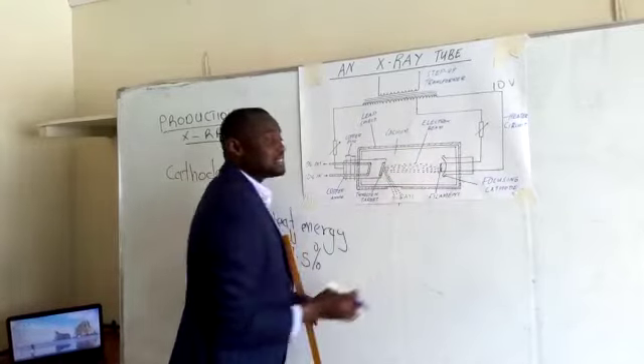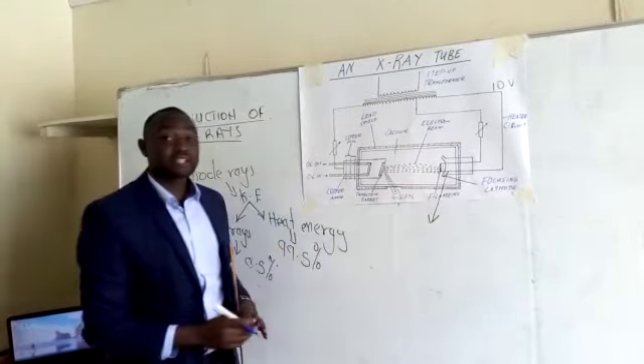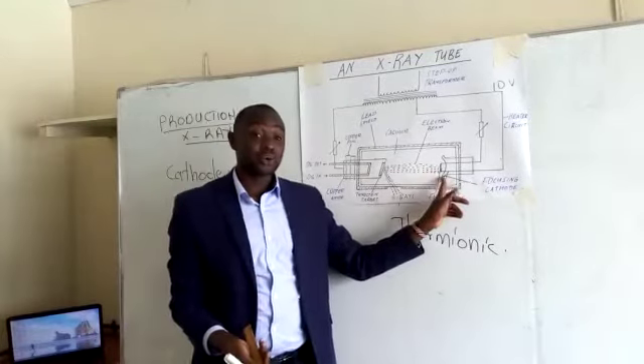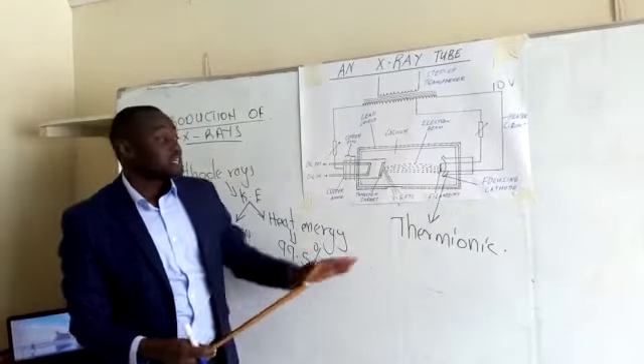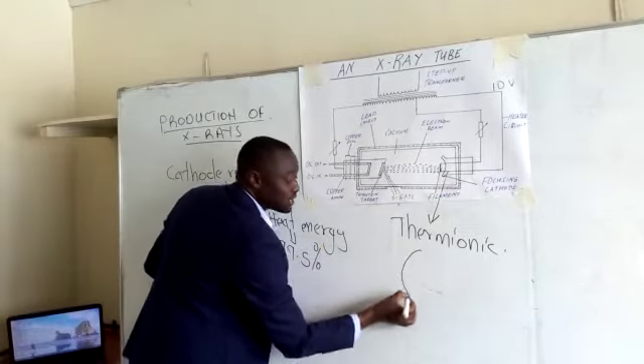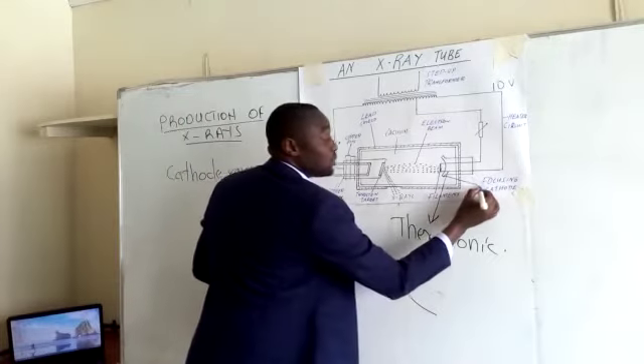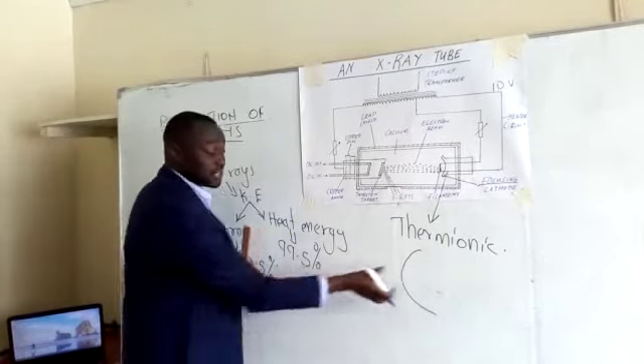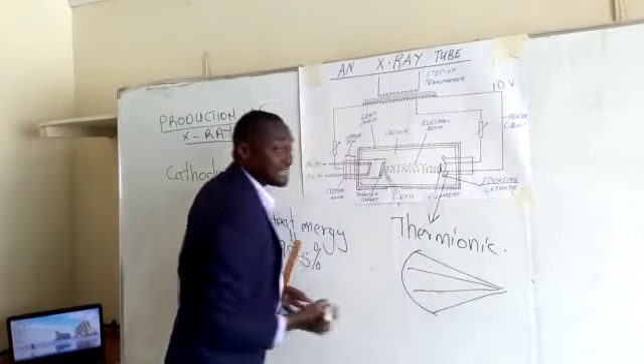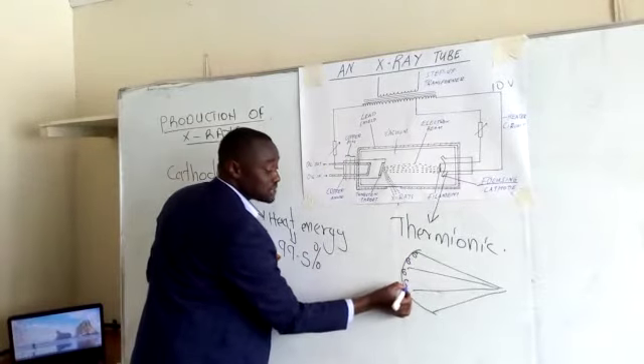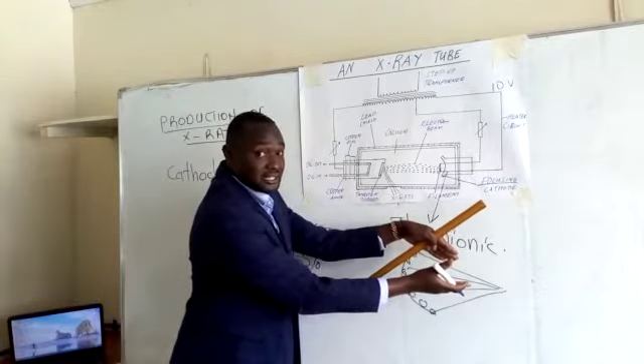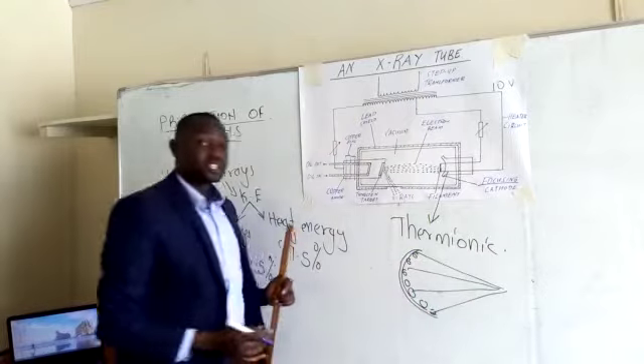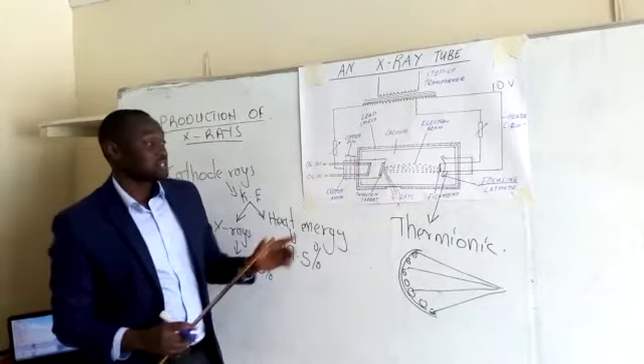This low voltage heats the cathode, which produces electrons through thermionic emission — just as in a CRO, we need a metal with a low work function. The cathode is shaped concave, which is why we call it the focusing cathode. Just as a concave reflector converges light, the concave shape focuses the electrons produced by thermionic emission onto the metal target.